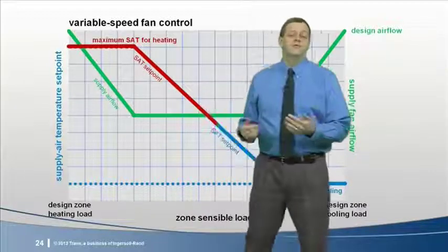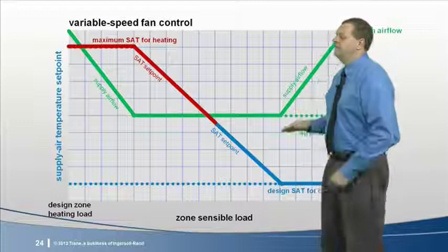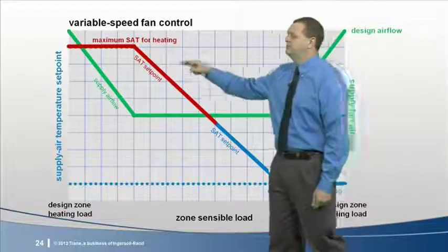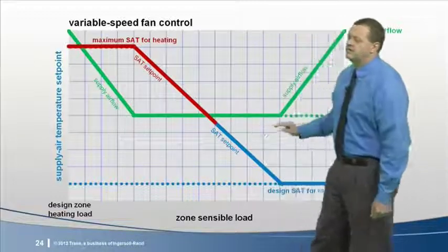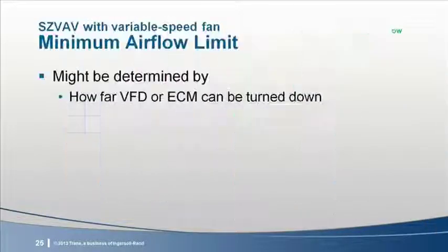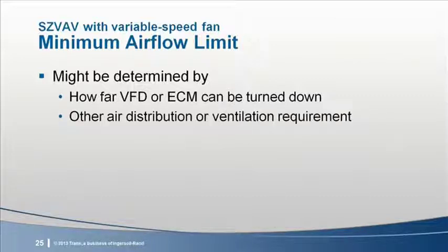Okay, let's talk a little bit more about these two limits, the minimum airflow and the maximum supply temperature for heating. This minimum airflow limit might be determined by how far the VFD or ECM can be turned down. This will be equipment specific and could be due to a number of reasons. It might be to ensure motor reliability, or in the case of DX equipment, for reliability of the refrigeration system. Or in some applications, this limit might need to be high enough to meet some air distribution or ventilation requirement.